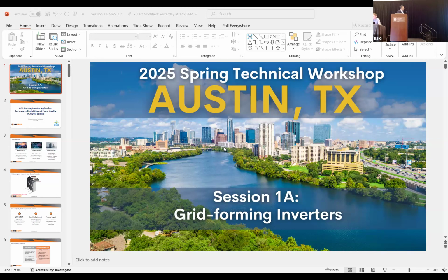So you can see after clearing the fault, the system becomes unstable. Is it similar to the blackout that happened to the Chilean network 2 weeks ago? The protection system doesn't work. After that, the network becomes islanded into 2 parts and becomes unstable. So after that, we replaced 4 grid following converters with 4 grid forming inverters, battery energy storage actually. And then you will see for this case, the system is stable.